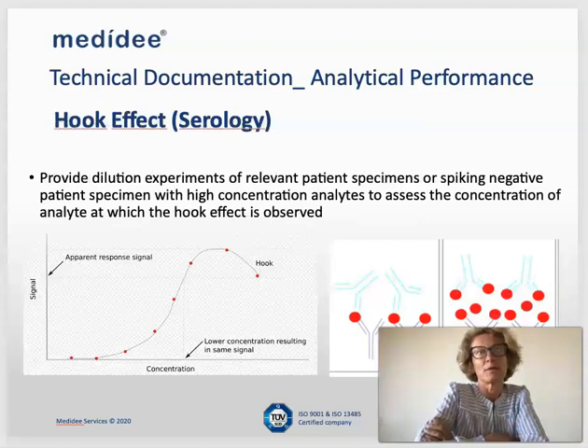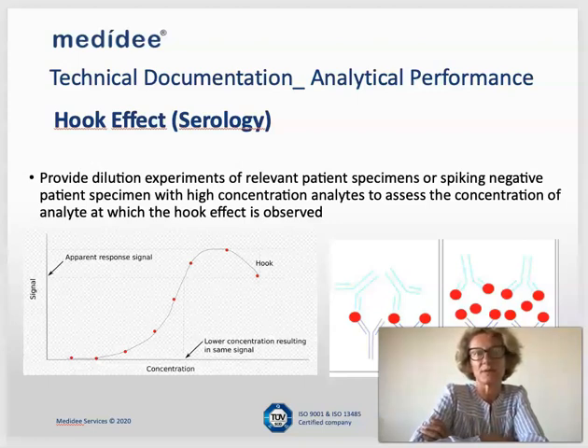A major drawback, in fact, for serological tests is the hook effect, and clearly this has to be assessed in the case of serological tests. This hook effect, in fact, happens when an important concentration of the analyte is present in the sample. While doing that, in fact, it washes away the result, and as it's presented here, with a very high concentration of analyte, you will arrive to have a signal which is lower than the signal that we may have with a lower concentration of the analyte. And in some cases, of course, it brings you to have a false negative result. So as false negative results are an issue for COVID-19 detection, the hook effect should be investigated before putting a device for COVID-19 detection on the market.